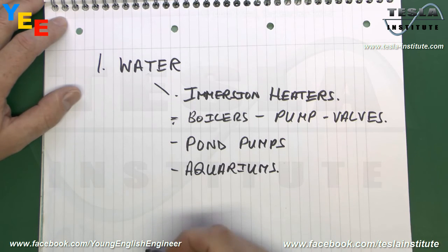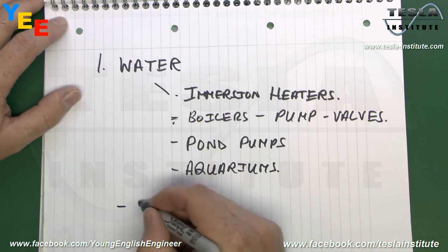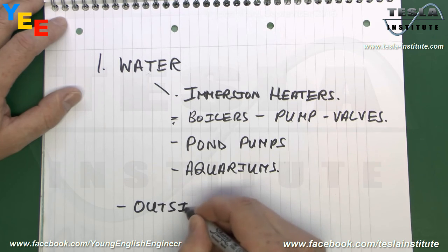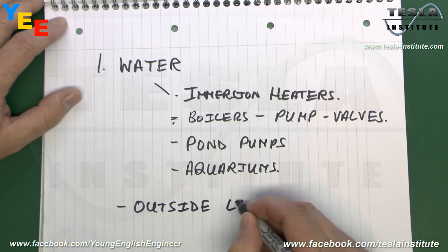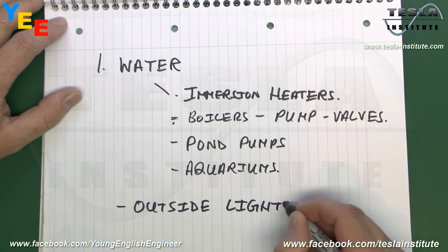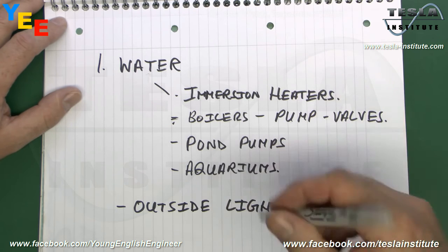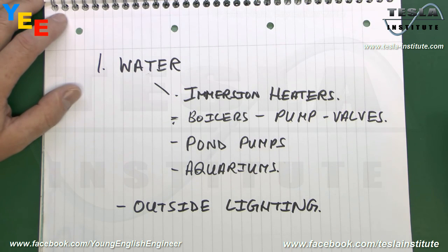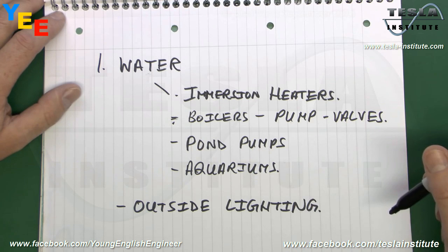And following on from the water theme, the other usual item is outside lighting. As being outside, of course, it gets wet every time it rains, and a lot of lights are not particularly well designed, so water can get in there. And it only requires a tiny amount of water on, say, a couple of connections or on a few exposed ends of a wire, and your insulation resistance can drop down to extremely low levels.